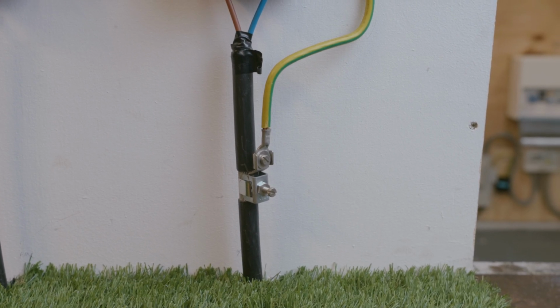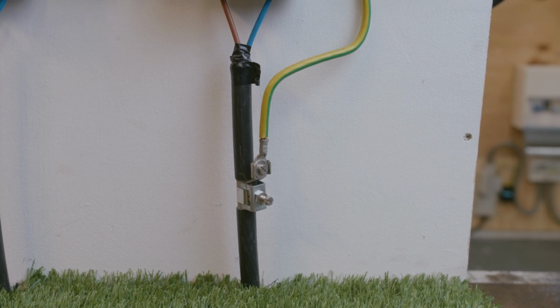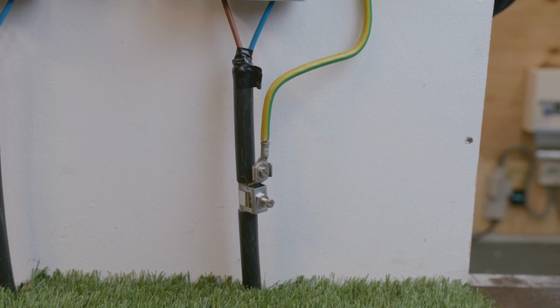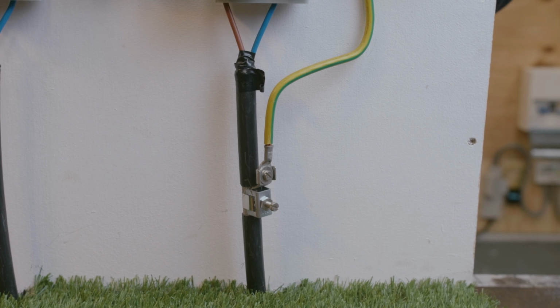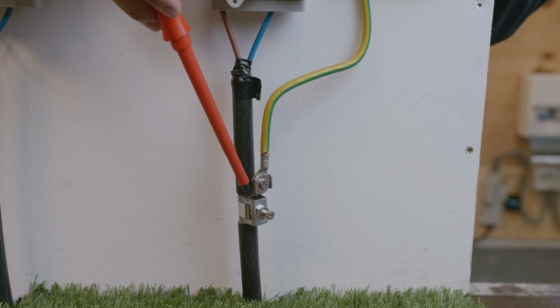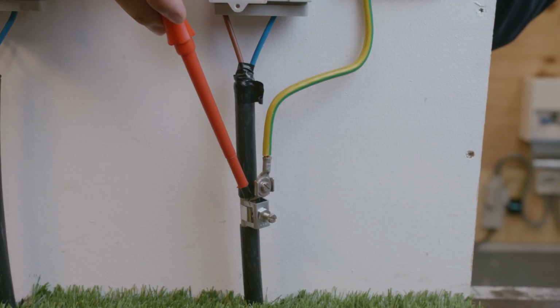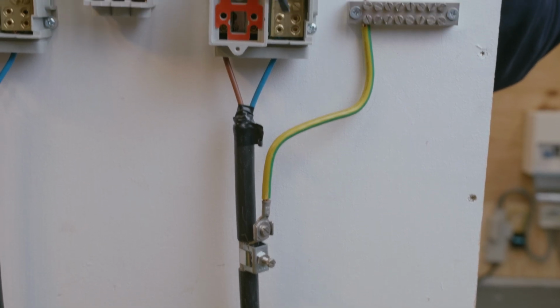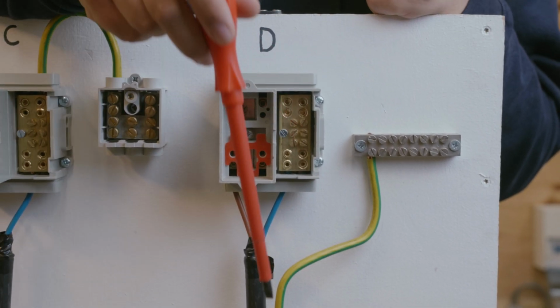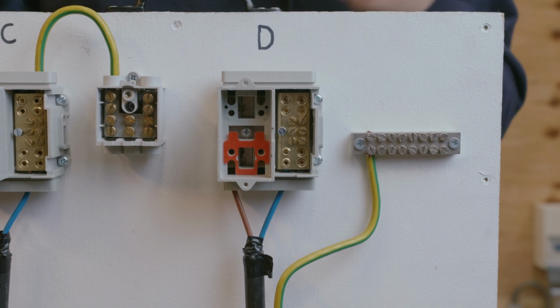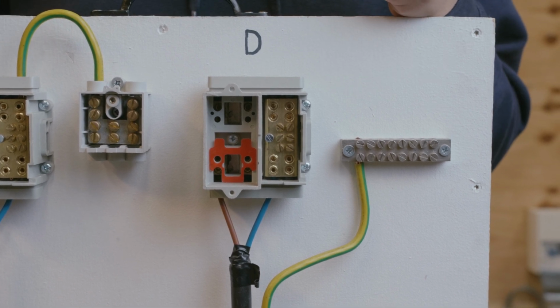This can also be a lead cable as well, but basically they're using the armourings of the cable as the earth. So the earth connection there is going on to the armourings of the supply cable coming in, and the neutral conductor is completely separate to the earth. So like I mentioned before, that would make it a TNS.